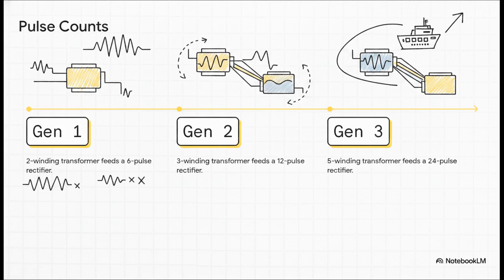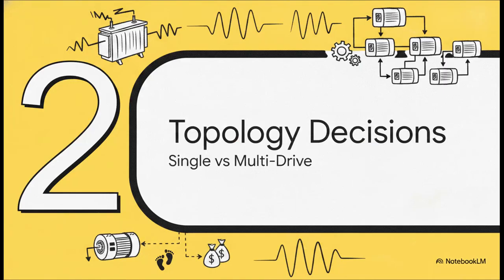Step up to a 3-winding transformer, and those 2 secondaries are actually phase-shifted from each other, feeding a 12-pulse rectifier. That phase shift mathematically cancels out several harmonic orders entirely. And for the absolute cleanest current draw, you specify a 5-winding transformer feeding a 24-pulse rectifier. More phase-shifted secondaries literally mean more harmonic orders are permanently canceled before they ever even have the chance to reach the ship's switchboard. Next up, let's look at topology, specifically contrasting single-drive versus multi-drive filtering.